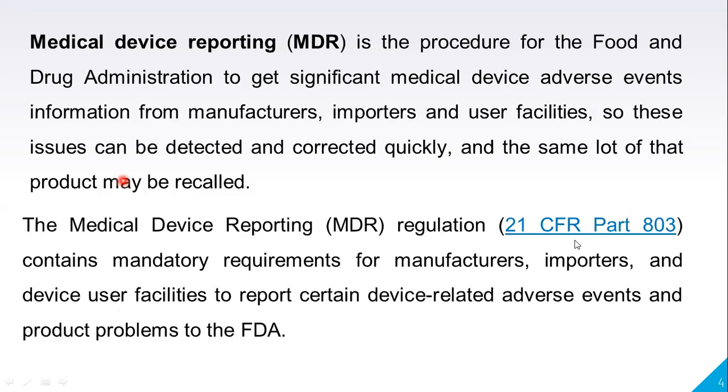21 CFR Part 803. Remember, this is a very important point. When anybody can ask you or question you, as per which regulations the user means already mentioned here: a manufacturer, importer, user facility, or anyone, patient or supplier, they may lodge the complaint to the FDA.